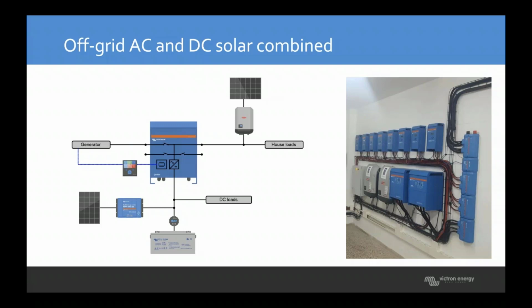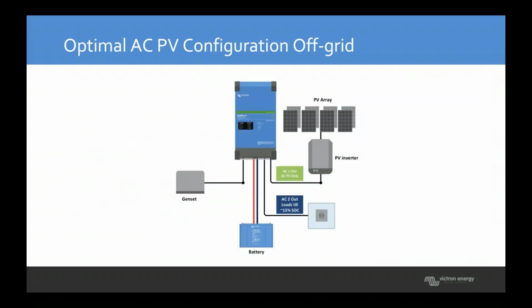Now, if you have a generator as well, that's another way to do it. But to start a generator is a lot more inconvenient for an end-use customer than just to wait until the sun comes out to bring the system back online. Or if there's nobody on site at all, that's an even bigger issue to start a generator. Generator runs out of fuel if it's an auto start. Having that DC MPPT allows for that black start capacity. Now, if you don't have a DC MPPT, another option is to do it like this.